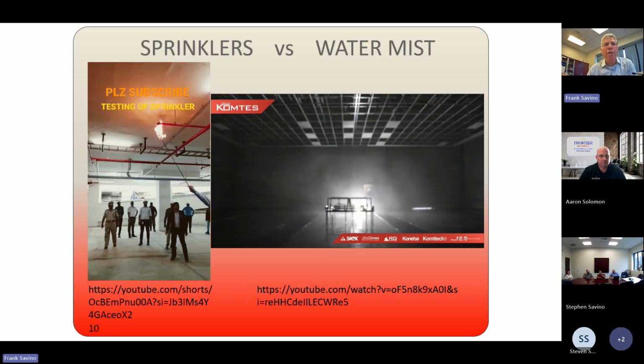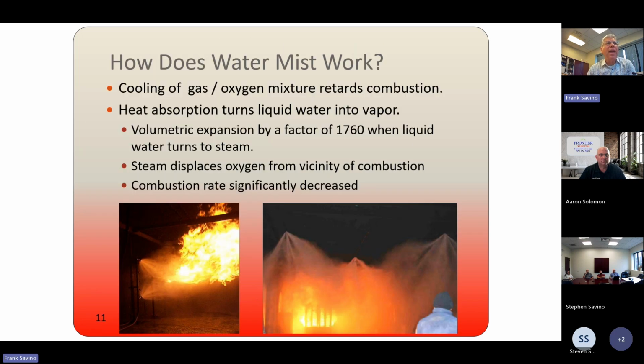But if you're using mist for an occupancy, you would want to have the automatic nozzle that has the fusible element in it, just like you would on a regular sprinkler system, because that is what holds it closed. Yes, that is correct. Normally, you really need to conceptualize water mist as being just like a sprinkler system. It works the same way. Principally, you have wet type water mist systems, pre-action type, deluge type. Anything you could do pretty much with a sprinkler, you can do with mist. The main difference is in the size of the droplets and the amount of water that you need to put the fire out or to design your system to.